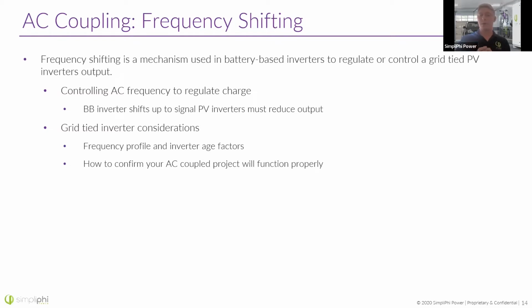What happens? Well, the battery-based inverter is going to sense that the batteries are full, and it's going to send a signal to the microinverters to tell them to stop producing power. That signal is called frequency shifting. So the battery-based inverter is going to, instead of producing 60 hertz, usually increase frequency slightly. So maybe 60.1 hertz, and it'll say, okay, 60.1 hertz, I'm going to produce a little less power. 60.2, half as much power. 60.3, a quarter as much power. And 60.4 or 5, shutting off completely for the microinverters.